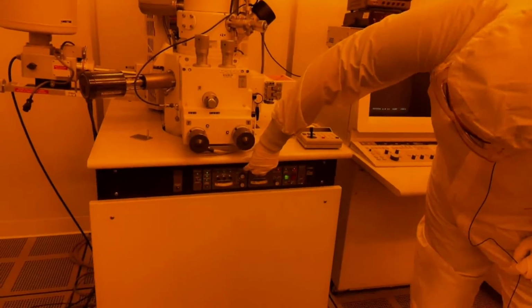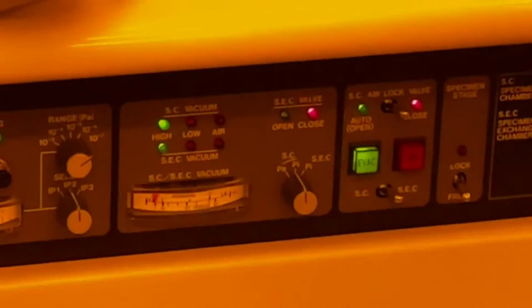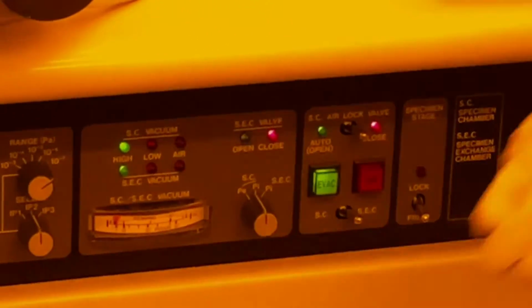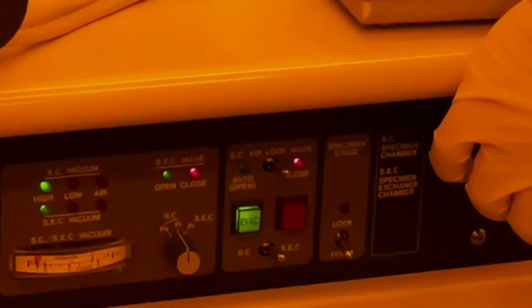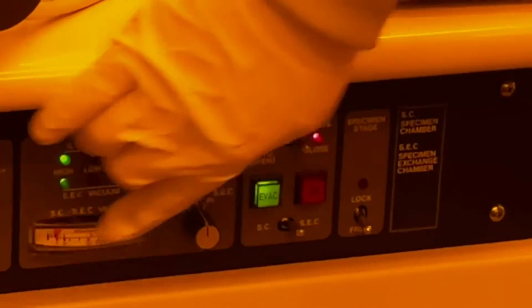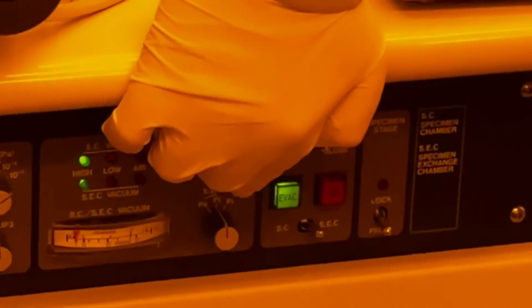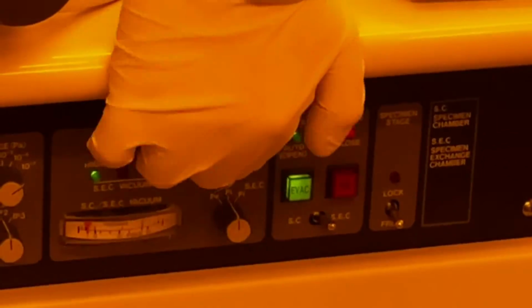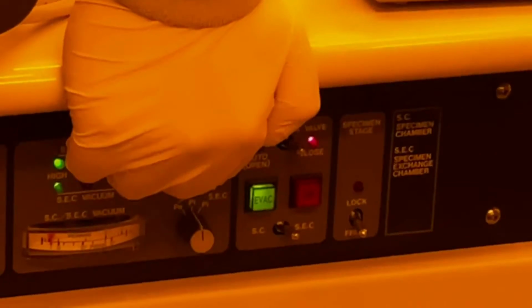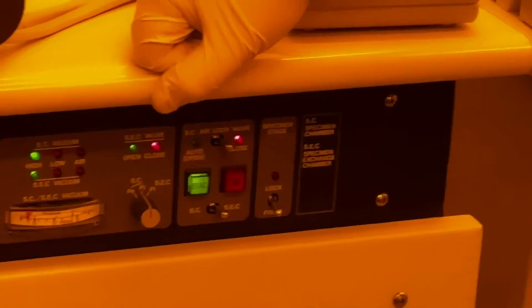The proper vacuum is determined by these indicators. So you basically have air, low, and high. Of course, when you're operating it, it has to always be in high. The low vacuum indicator indicates that it's low, but it's not at atmosphere. And then, of course, air indicates that it's at atmosphere. You also have this gauge here for these 3 Pirani and penning gauges. So you have 2 gauges for the sample chamber, a Pirani gauge and a penning gauge, and 1 gauge for the sample exchange chamber, which is just a Pirani gauge. By switching between them, you can get the different vacuum levels of each one of the gauges.